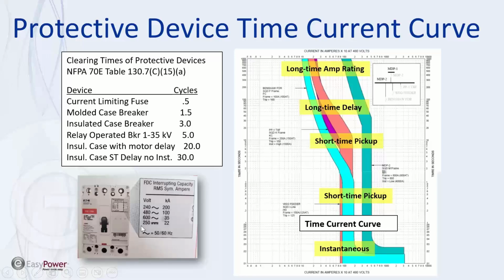So once you determine what your available fault current is, then you make sure your boxes and equipment and breakers and fuses are all rated for the available fault current. As a matter of fact, you probably want to exceed that by 30 or 40% just to account for future changes in your load situation. So that's kind of in a nutshell what we're going to do. So these should be all coordinated, so the one feeding the equipment that you're working on that has a failure is the one that trips first.